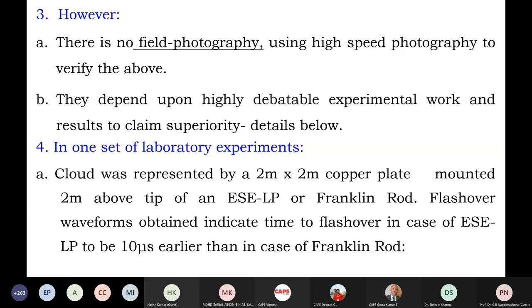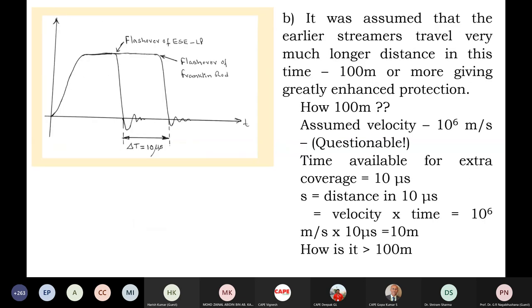In one set of the laboratory experiments, which have been claimed to show the superiority of the ESE system, a cloud was represented by a 2 meter by 2 meter copper plate mounted 2 meters above the tip of an ESE LP or, afterwards, a Franklin rod. The flashover waveforms obtained indicate the time to flashover in case of the ESE LP to be 10 microseconds earlier than in case of the Franklin rod. Gopakumar also pointed that out. I have shown the possible figures here. The time to flashover is 10 microseconds earlier.